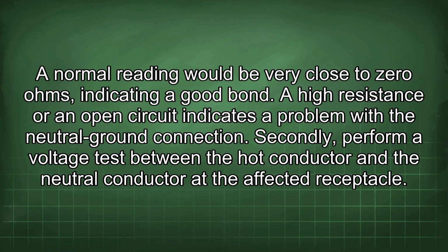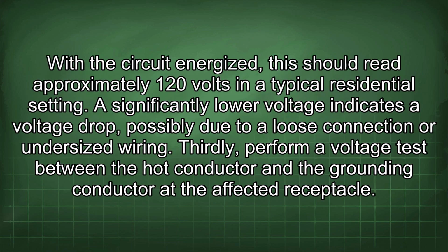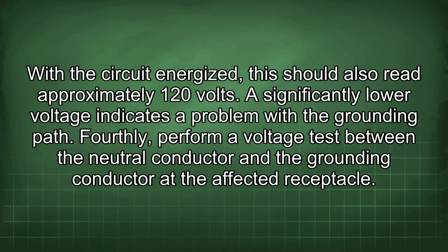Secondly, perform a voltage test between the hot conductor and the neutral conductor at the affected receptacle. With the circuit energized, this should read approximately 120 volts in a typical residential setting. A significantly lower voltage indicates a voltage drop, possibly due to a loose connection or undersized wiring. Thirdly, perform a voltage test between the hot conductor and the grounding conductor at the affected receptacle. With the circuit energized, this should also read approximately 120 volts. A significantly lower voltage indicates a problem with the grounding path.